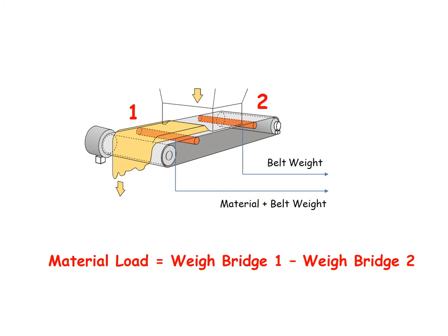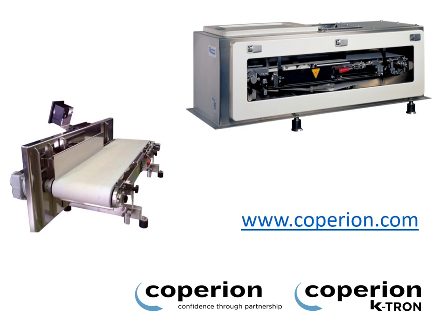Adding a secondary weigh deck that weighs the empty belt before material is loaded onto it is a simple yet very effective solution to this problem. The material load then becomes a simple subtraction of the empty belt from the loaded belt, and is therefore independent of any changes of weight to the belt. You've effectively created a continuous online tare. And that's why two weigh decks are better than one. Thank you for listening. If you'd like any more details, please visit us at www.coperion.com.